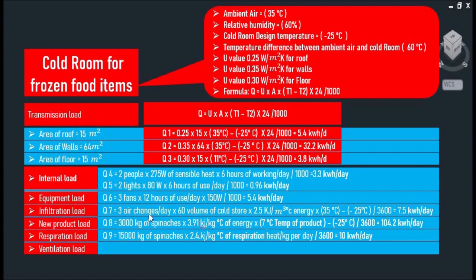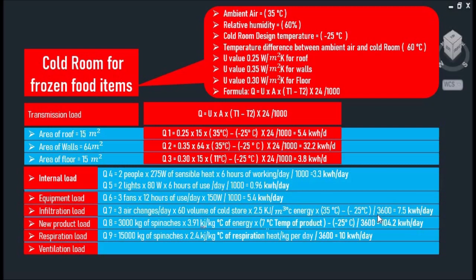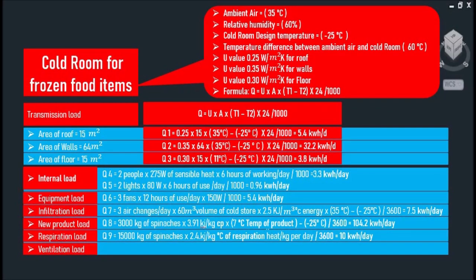As you can see, we have three air changes per day multiplied by the volume of cold store multiplied by 2.5 kJ per cubic meter multiplied by ambient air minus the indoor design temperature and divided by 3600. That comes to 7.5 kWh per day. Our next product load.